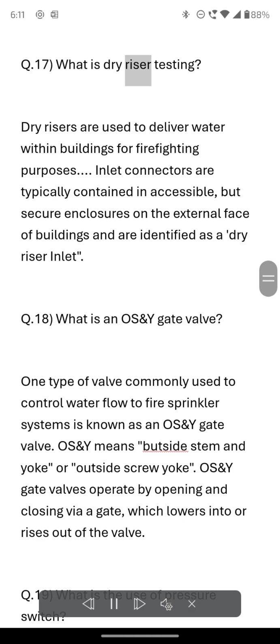Q.17. What is dry riser testing? Dry risers are used to deliver water within buildings for firefighting purposes. Inlet connectors are typically contained in accessible but secure enclosures on the external face of buildings and are identified as a dry riser inlet.